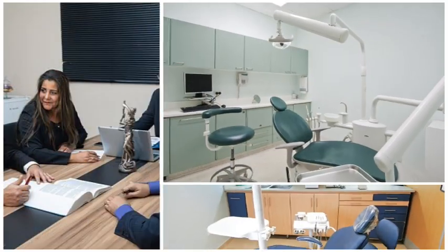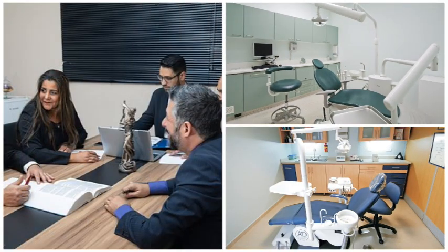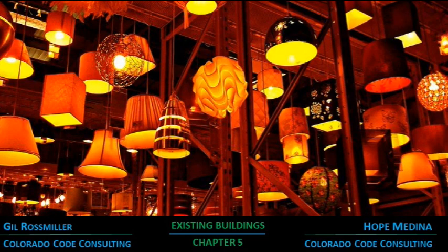Then we have commercially things that we call just a change of use. Okay? Yes. So let's say we had a lawyer's office, and it now becomes a dentist. It's still a B occupancy. Mm-hmm. No occupancy change, but has the use changed? Oh, absolutely. Sure it has. As far as the energy code is concerned, lighting is probably the biggest thing in Chapter 5. It says if the watts per square foot have changed from that use to the other use, even though it's within the same occupancy, okay? The lighting needs to come up.